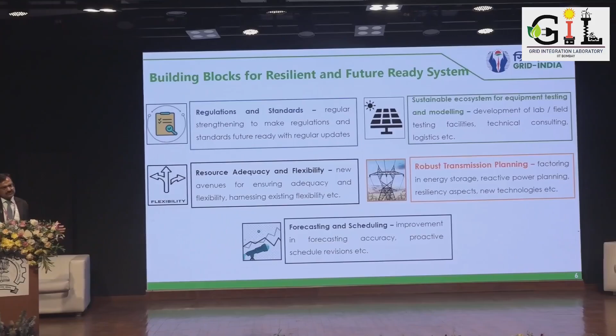Another important parameter is that, as per the CEA standard, this needs to be checked each and every year: what the harmonic percentage is at each substation and at each power plant. But this is not happening. So we need to work towards all the transmission utilities also measuring the actual harmonics at each of their EHV substations. Then only will we know the baseline, where it is coming from, where we need to take action and what action needs to be taken.